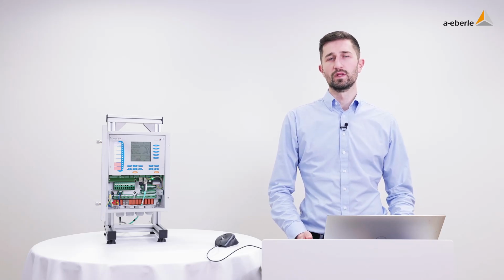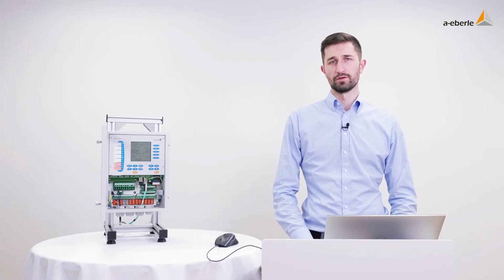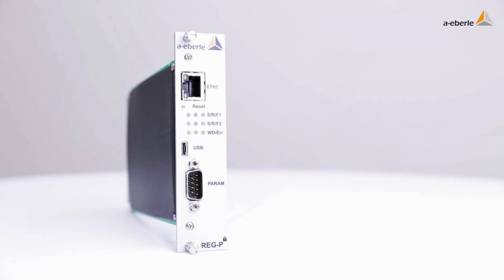But which of the 2 or 4 physical ports is the Ethernet port number 1? Let me give you an overview which physical port is the first Ethernet port. Eberle sells different SCADA cards, and every SCADA card is a little bit different. Let's start with the REG-P card. This card has only one Ethernet port, so the question is trivial. This port is Ethernet port number 1. This is also true when this card is installed in a REGDA.